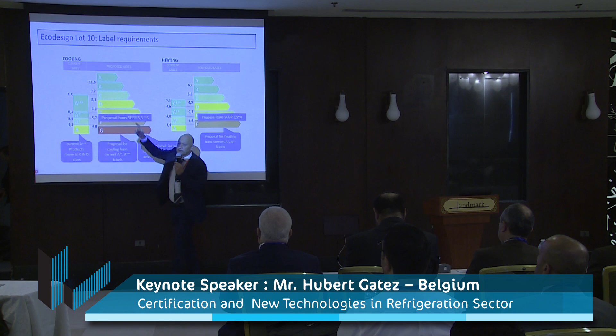This is a big problem for us in the industry. 11.5 is too high. We consider it's too high. The same for heating. Why do we consider it's too high? It's because this does not reflect reality. 11.5 will lead to, let's say, a testing methodology which is not reflecting reality. What I say here is that reaching energy level A, this improvement, will clearly impact the comfort level. It will not lead to savings in real life. These results, theoretical energy savings, are tested in laboratories, not in real life.